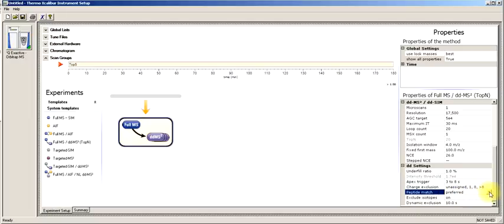Peptide match, this is MIPS, monoisotopic precursor selection. If you're doing a discovery experiment, leave this on preferred. What that's going to do is allow you to not spend your time fragmenting your ion of interest plus that ion of interest with 1 C13, 2 C13, 3 C13s. Don't waste all your time fragmenting the same ion over and over again just because you've found the isotopes of that.